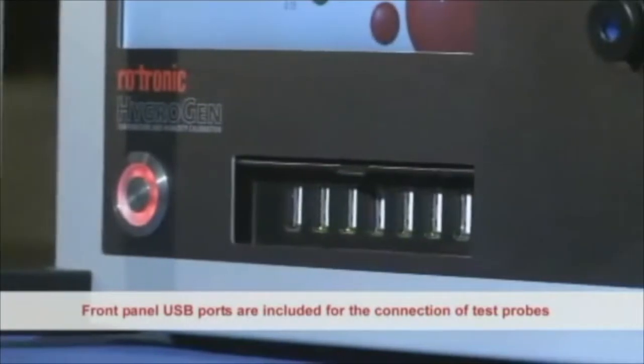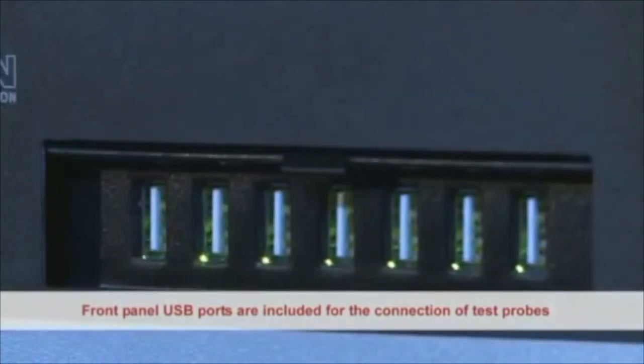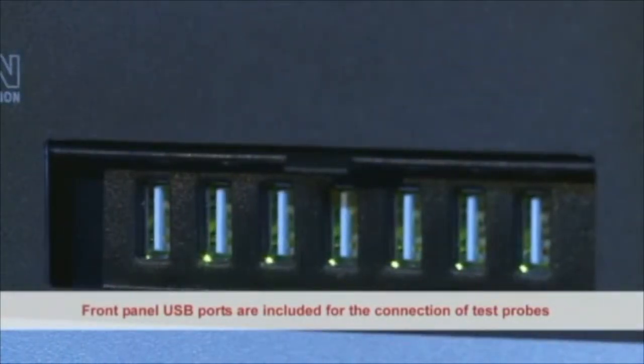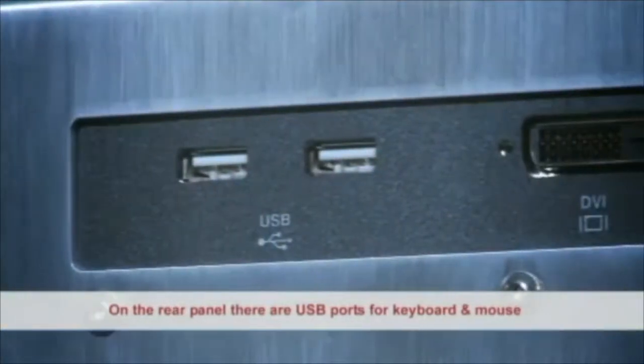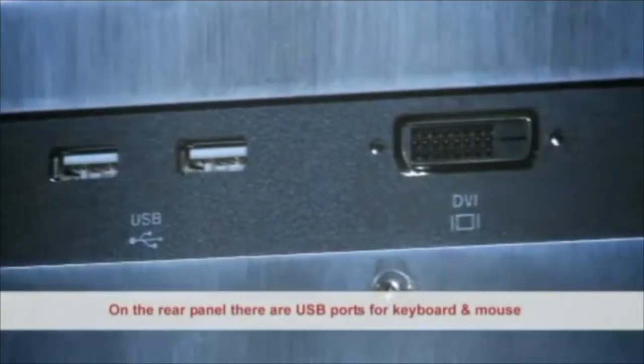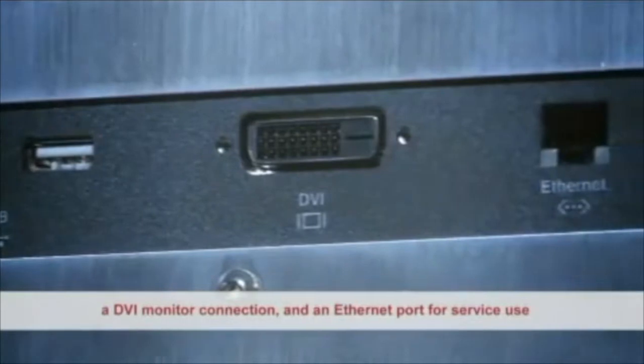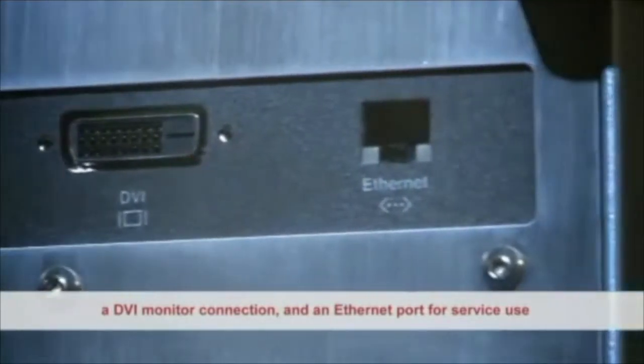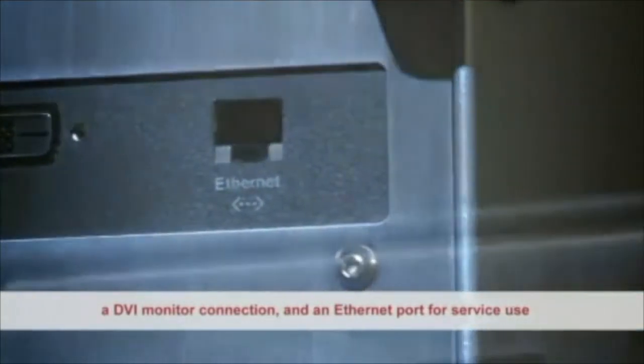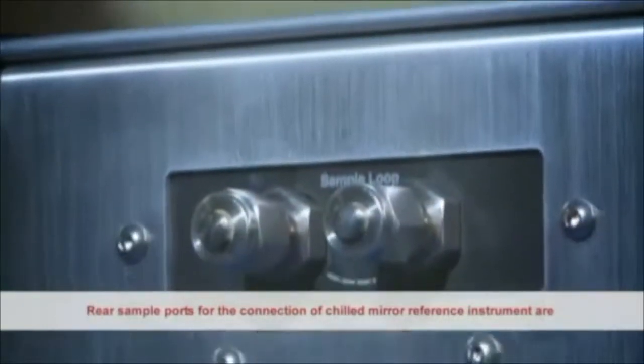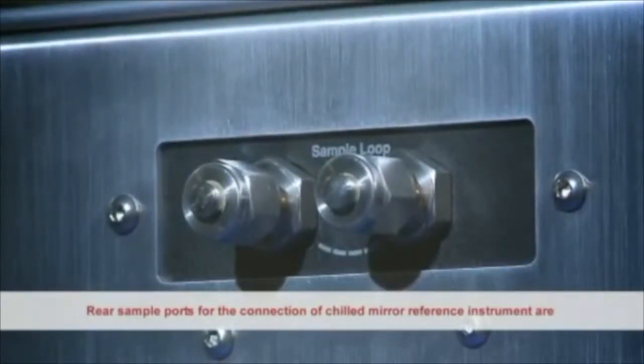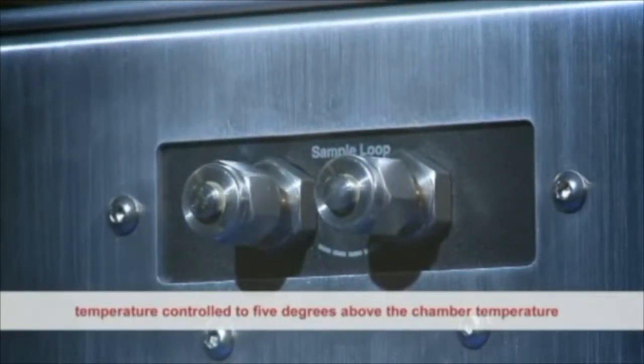Front panel USB ports are included for the connection of test probes. On the rear panel, there are USB ports for a keyboard and mouse, a DVI monitor connection, and an Ethernet port for service use. Rear sample ports for the connection of a chilled mirror reference instrument are temperature controlled to 5 degrees above the chamber temperature.